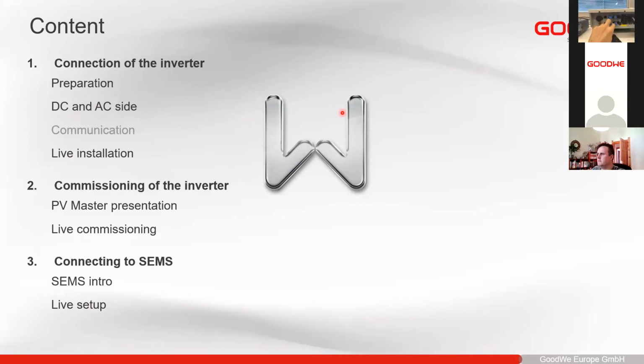Here you have the two different PV connections, one MPPT and the second MPPT. You have plus and minus. I'm not sure if you see it, but here on the bottom side, it's sort of printed on in the metal what it is. Here's one MPPT, you see PV1, PV2, and then here it even says battery connection. So here you also have the battery connection. Here is then the communication module that goes in here, usually a Wi-Fi communication, or you can also unscrew the screws here. There are 4 normally. I just took away 2 to save some time. And then you can connect the LAN module here as well.